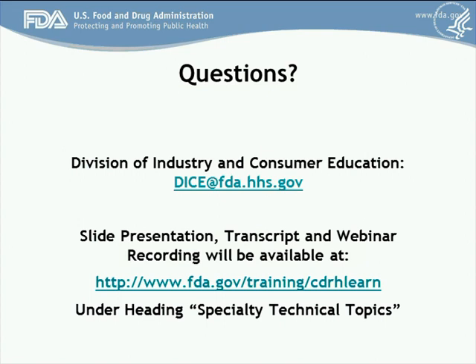It is the intention of the agency to look at things in the pre-market stage such that they support the intended use of the device in much the same way as we have them. Certainly for the AED functions, they need to have a reasonable assurance of safety and effectiveness, but we would not expect any change to, say, the monitoring functions or the ECG functions that currently exist on some of the monitor defibrillators. We would not expect that pre-market bar to be any different.